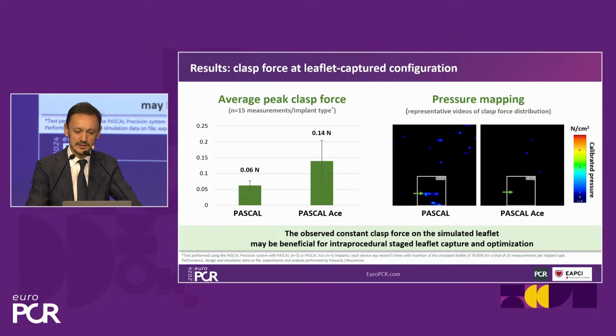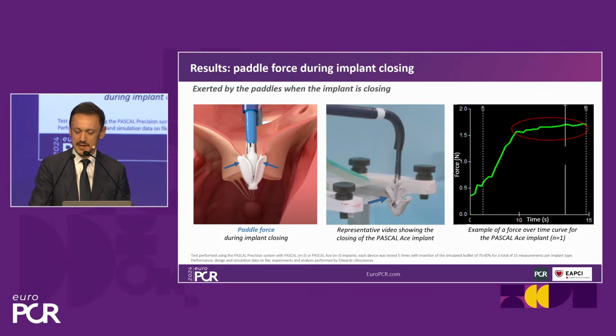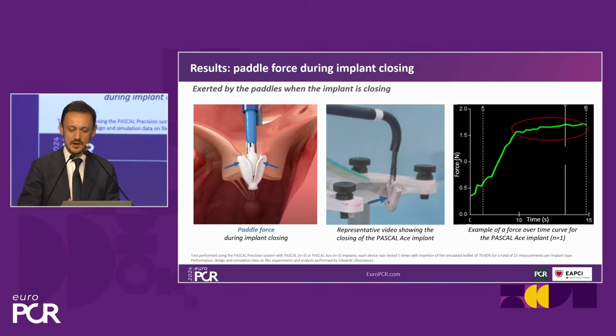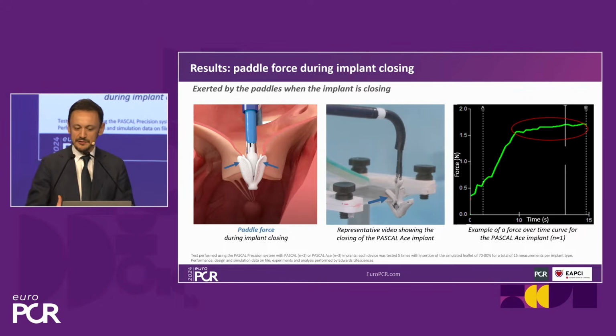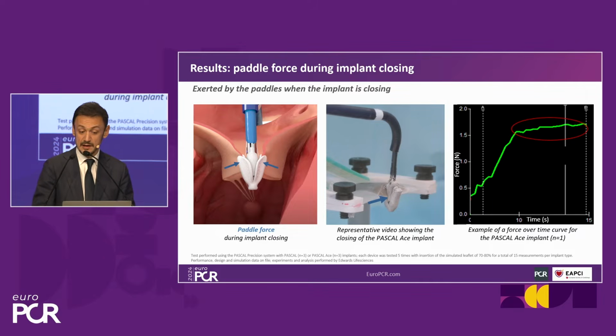And then the second force that we are going to check, which we want to be, in this case, constant, uniform, but extremely atraumatic, because especially in some anatomy and in some difficult situations, we may be afraid of leaflet tearing or leaflet damage, is the paddle force, so the force of closing: which amount of force we are going to apply on the leaflet when we close. Obviously, we should be careful to release the tension and to do it carefully, but the feature of the device, the passive closure and the nitinol features of the device, are extremely important.